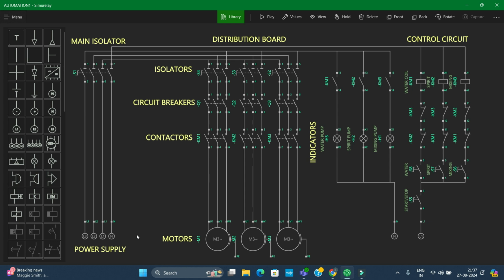If it's an industrial level and they have three phase, or the equipment is three phase, you have to abide with what they have. So I have my power supply here - it's a three-phase, four-wire system, because I'm catering for an unbalanced system. If it were only balanced, I could only have three-phase, three-wire.